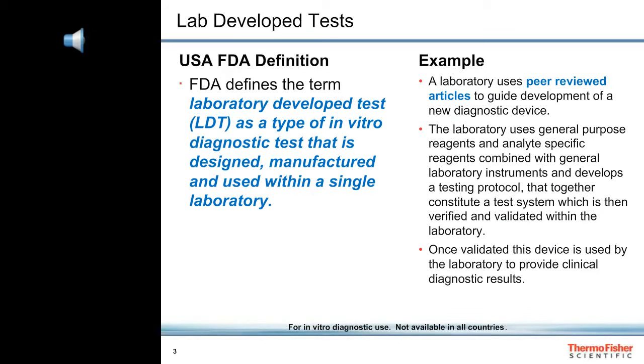When I say in-house methods, I mean laboratory developed tests, which the U.S. Food and Drug Administration regulates for in vitro diagnostic use. Those who develop clinical laboratory methods typically start with peer-reviewed articles to help them utilize their instruments, reagents, and other resources to run samples and generate data in order to come up with a reliable procedure to measure specific things in blood, urine, or other biological fluids. They must validate the entire system — which includes instruments, reagents, consumables, and standard operating procedures — in order to use the test for diagnostic purposes.